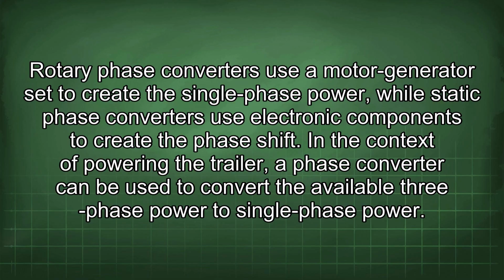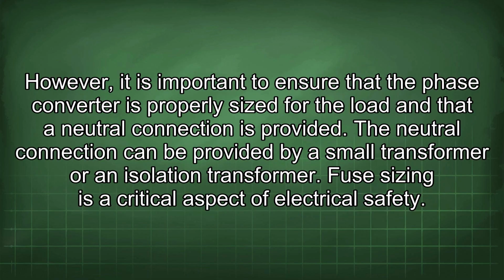In the context of powering the trailer, a phase converter can be used to convert the available three-phase power to single-phase power. However, it is important to ensure that the phase converter is properly sized for the load and that a neutral connection is provided. The neutral connection can be provided by a small transformer or an isolation transformer.